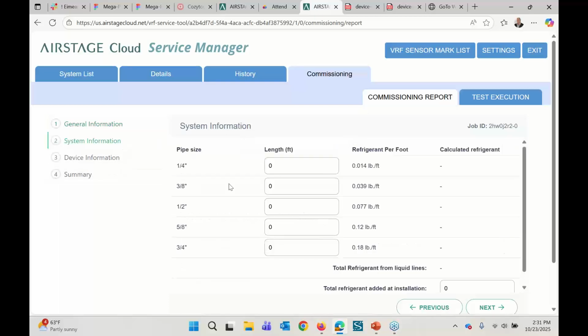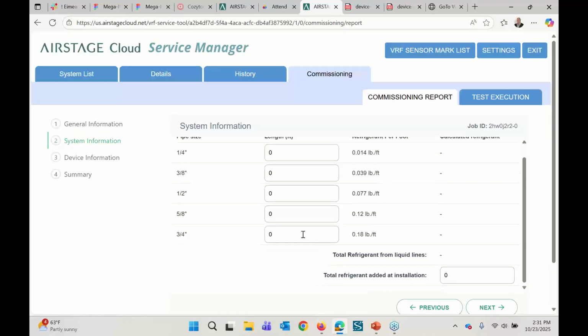On the second page, you add all your pipe length information. That originally comes from Design Simulator, which you verify on the job site by writing down the exact amount of pipe length used. If you load that into AIRSTAGE Cloud, it will do the calculations for you and tell you your total refrigerant charge for that job site.